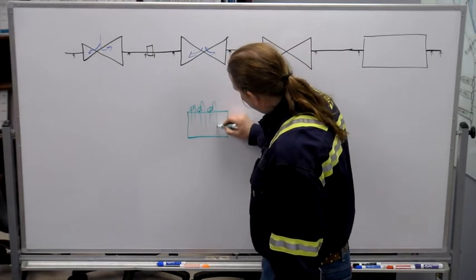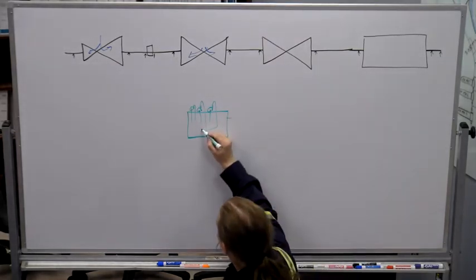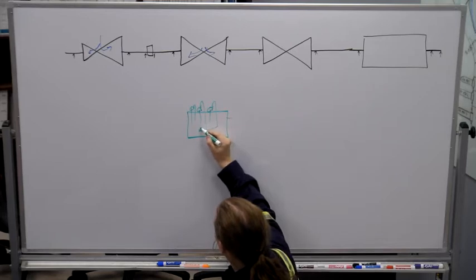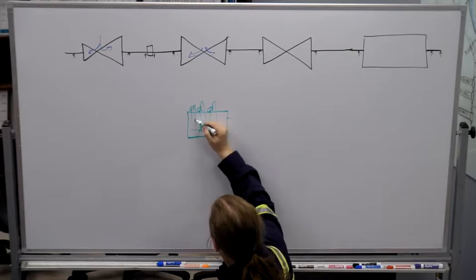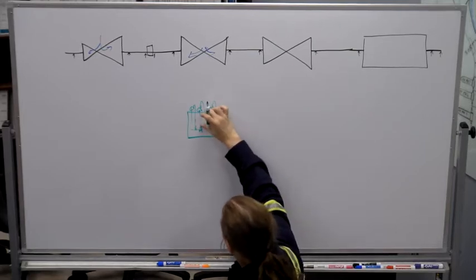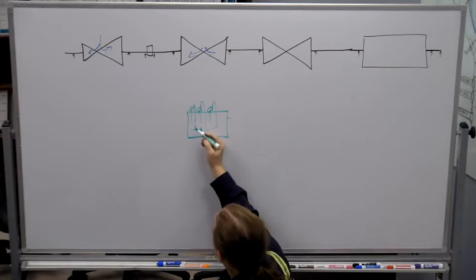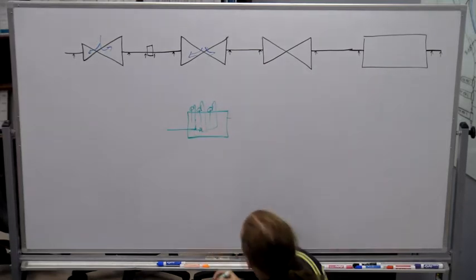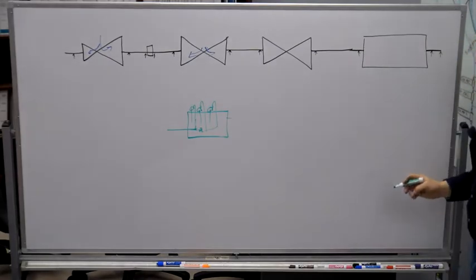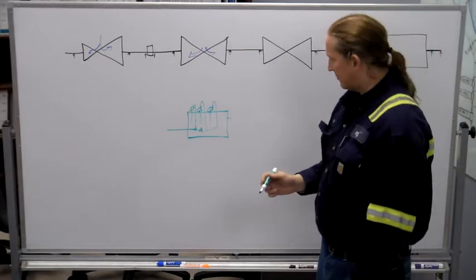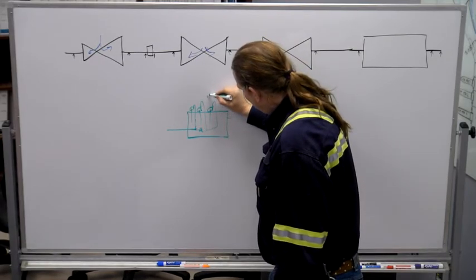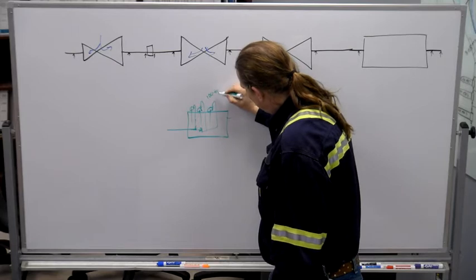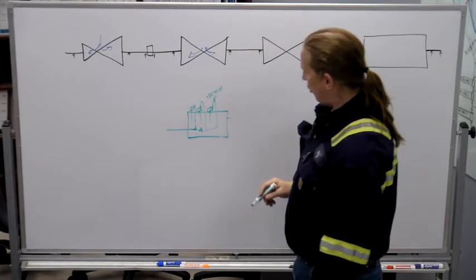So the alpha and bravo pump go and tie together. And then inside the tank there is a, they call it plug valve, but it's a pressure reducing valve. And then the emergency pump ties in downstream of that. And then we come out. So what kind of pressure are we talking about? About 105, 106 on the main lube oil pumps. So we're running between 100 and 110 PSI on the main lube oil pumps.